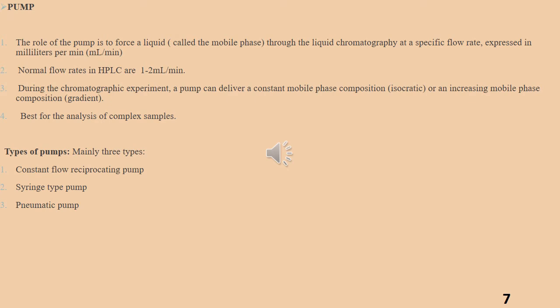Non-reciprocating or constant pressure pumps. A pneumatic pump is operated by gas pressure. Pressure from a gas line acts on a large piston which drives a piston of small area. The gas pressure is thereby amplified in the ratio of the areas of the faces of the piston, and high pressure liquid at constant pressure is delivered to the system.